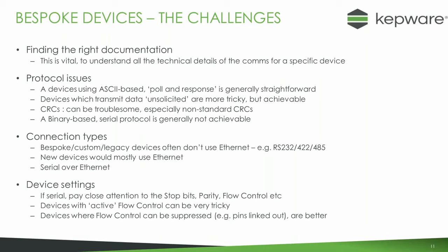After looking at connection types, examine the device settings, especially for serial devices — stop bits, parity, and flow control. If a device uses active flow control, where pins like RTS and CTS are toggled during the comms cycle, that can be quite tricky. However, if you can suppress flow control by linking CTS to RTS so the device is effectively always active, that's generally manageable.